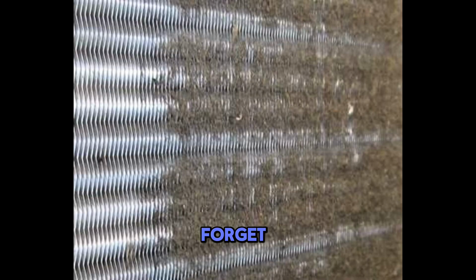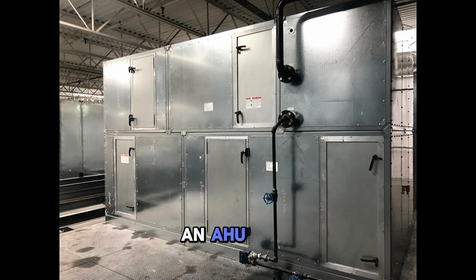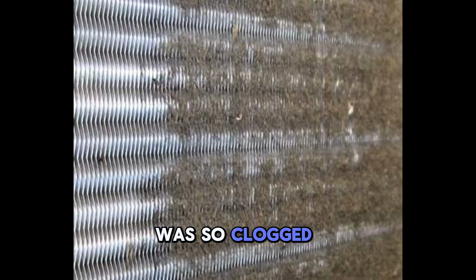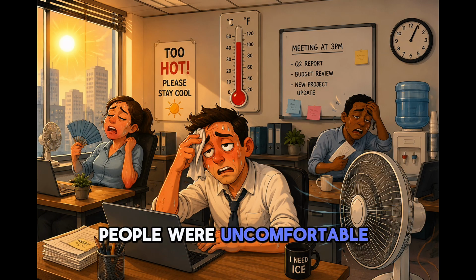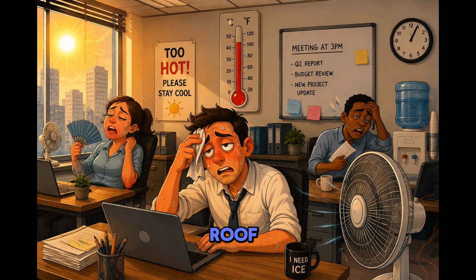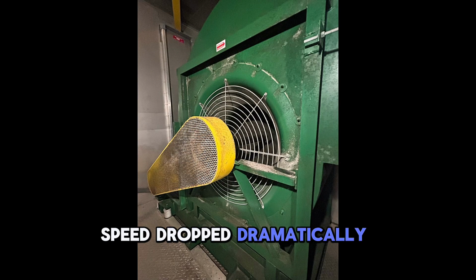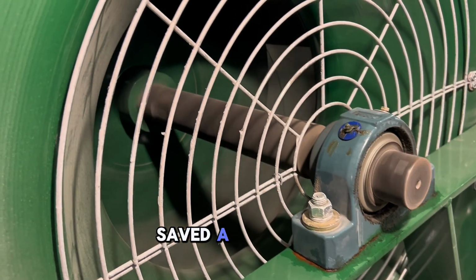I'll never forget. I went to a building with an AHU and the cooling coil was so clogged it looked like a black brick. Airflow was terrible, people were uncomfortable, and energy bills were through the roof. 2 hours with a coil cleaner and the supply fan speed dropped dramatically. And the building saved a fortune.